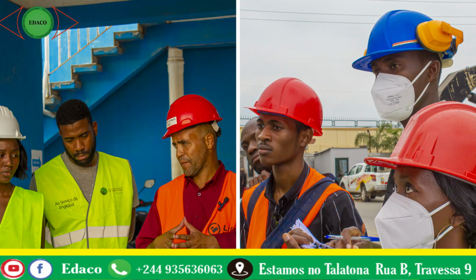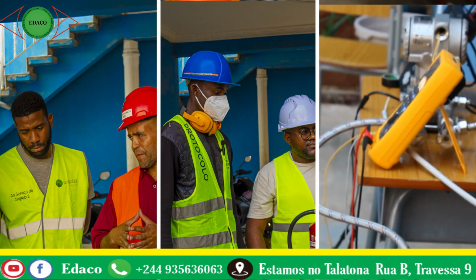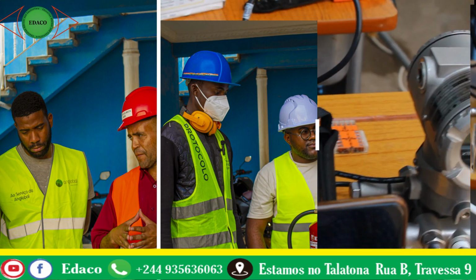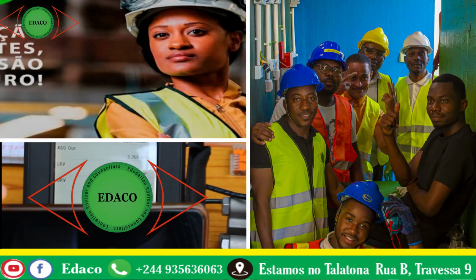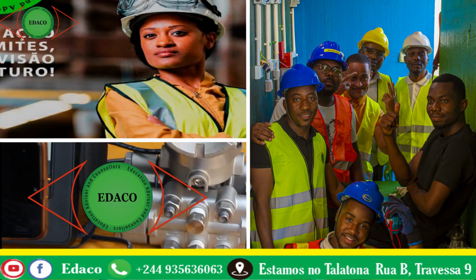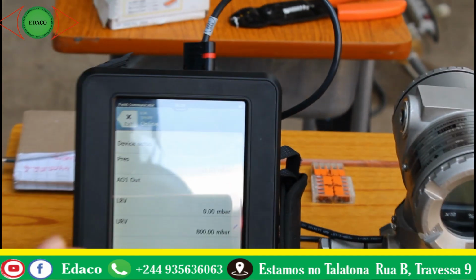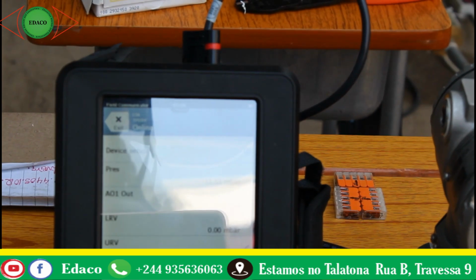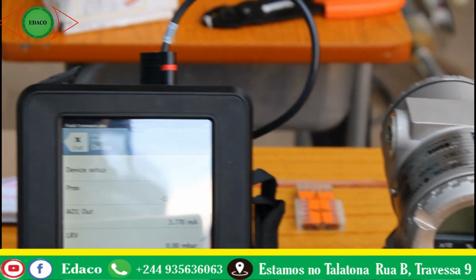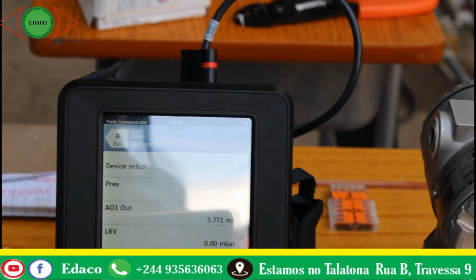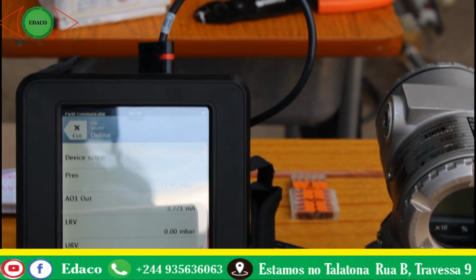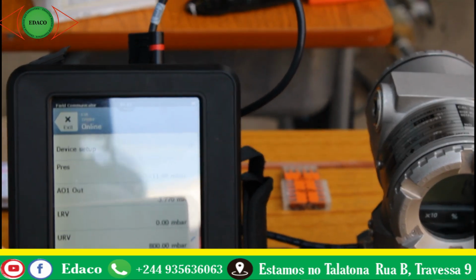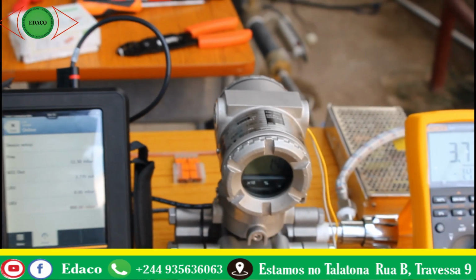As I was saying, if you look at our Trax, our lower range value is 0 millibars, and our upper range value is 800 millibars. Right now the pump is shut down, so no flow, no pressure. This is what we are reading currently.